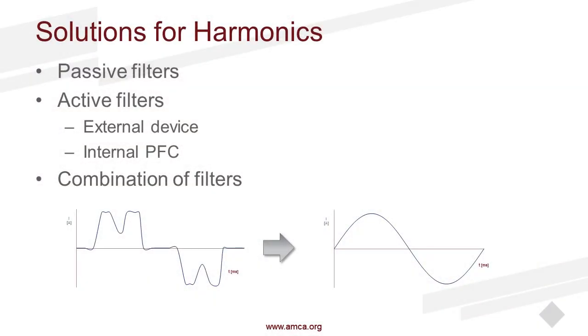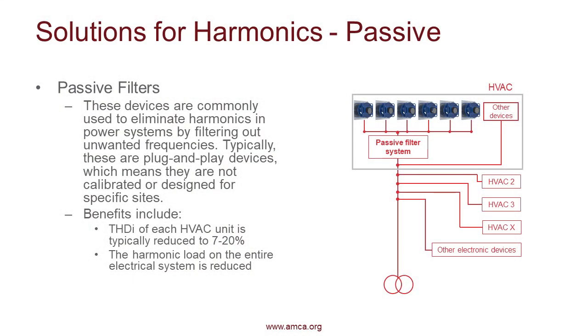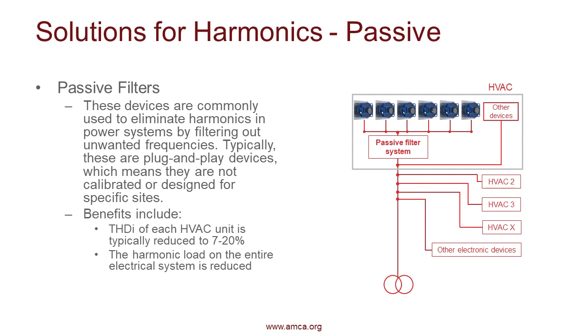So now we can start to look at the equipment manufacturer side and look at what solutions there are for harmonics within fan systems. So we have a few solutions. We have passive filters, active filters, which are external and internal. And then we can combine these options as well. So passive filters, these are typically a very simple, easy plug-and-play solution. There's no additional work except for installing it into your system, right? There's no calibration, you just plug it in. It's acting like a low-pass filter. So it's cutting out those higher harmonics, and thus it's reducing our total harmonic distortion current. So typically we see 7 to 20% of THDI with fan systems with the use of a passive filter. And with this, we are able to reduce the harmonic load on our electrical system.